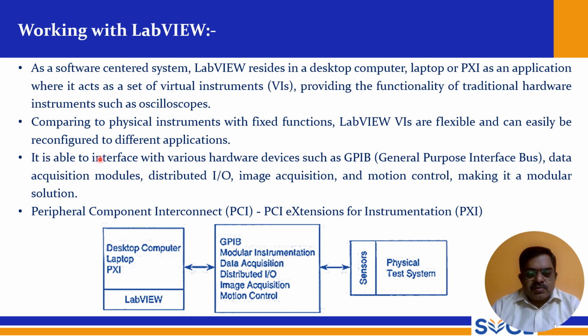It is able to interface with various hardware devices such as GPIB, the general purpose interface bus, data acquisition modules, distributed IOs, image acquisition, and motion control, making it a modular solution. And PXI is the PCI extension for instrumentation, that is, peripheral component interconnect.